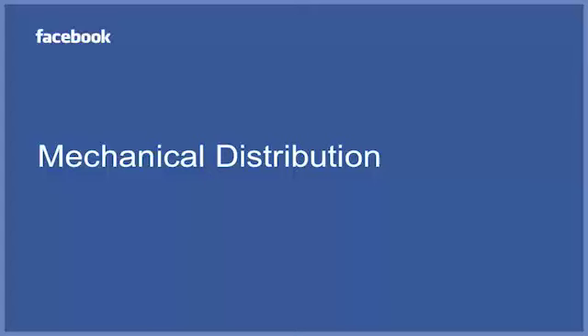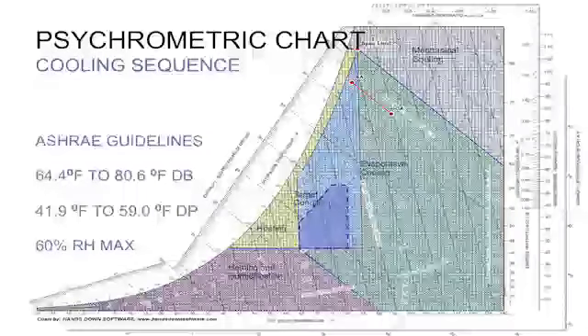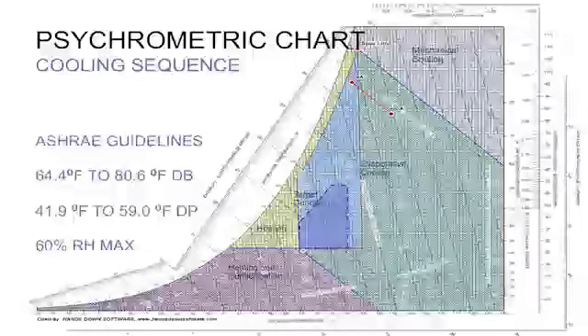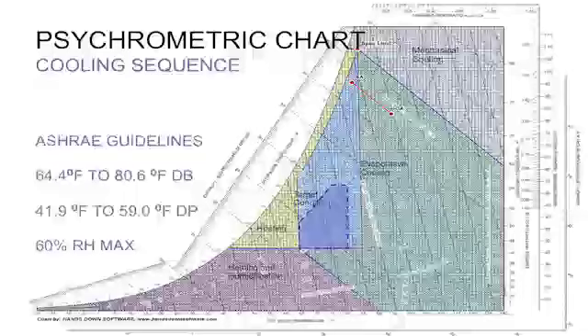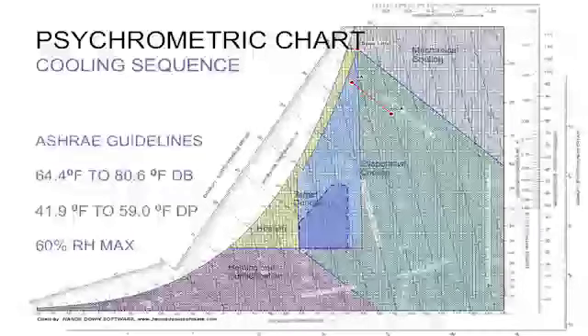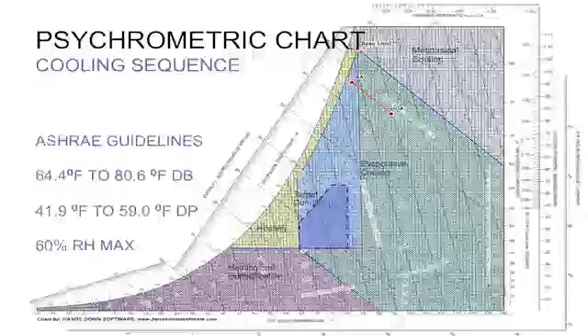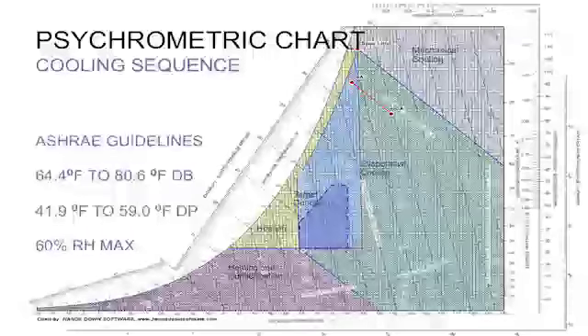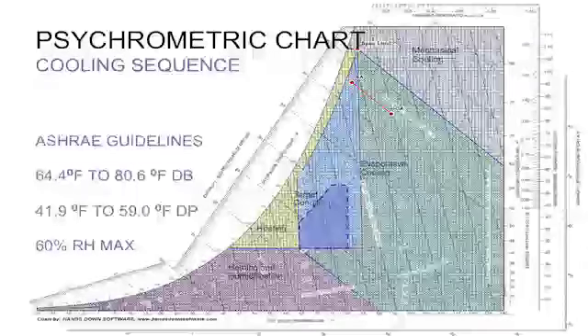So our mechanical distribution, our premise was that we would use 100% outside air. Looking at our psychrometric chart, the small polygon here really represents what ASHRAE's guidelines are for cooling a data center. By being in control of the application, the servers, and the facility, we recognized we have the opportunity to really broaden the ability of using free cooling. So this is the range in which we are delivering our cool air to our data hall.